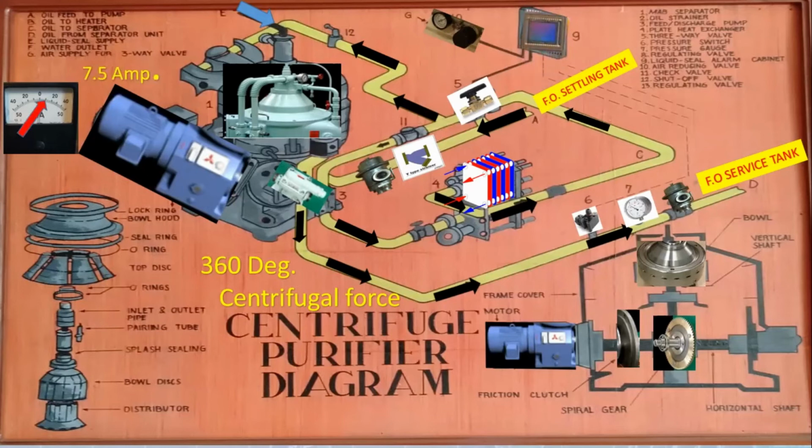Then we also check the liquid alarm monitoring screen. That's the time that the fuel oil shut-off valve opens for introducing fuel oil inside the fuel oil purifier.